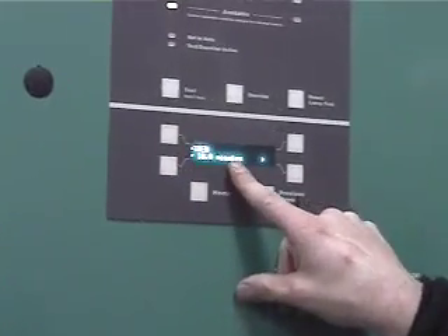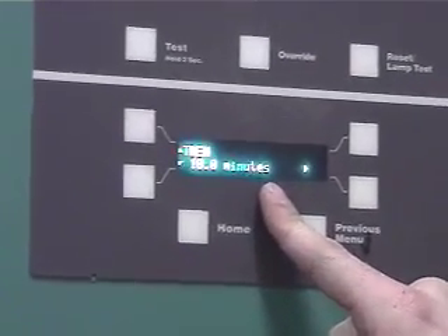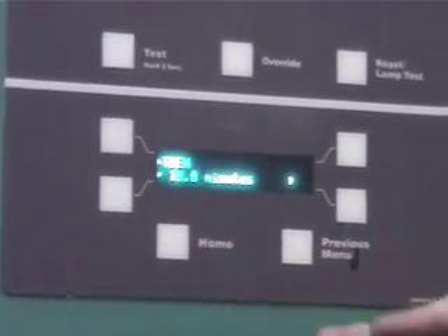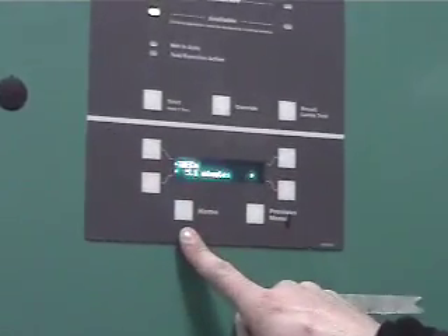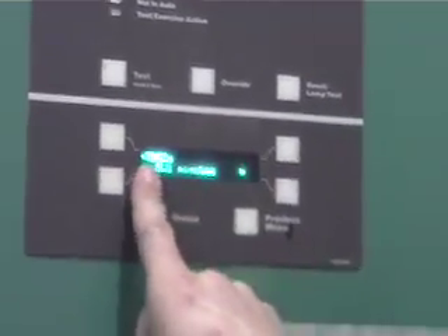At that point, when you're running on the generator, get back to that. When normal power comes back on 10 minutes later, it's going to retransfer just like that one. But then once it retransfers, it's going to stop in neutral again for 3 seconds, and then it's going to transfer back the rest of the way. Then it goes into its cooldown, where it runs for 5 minutes and then shuts off. So that's the one you can't override. It is what it is.